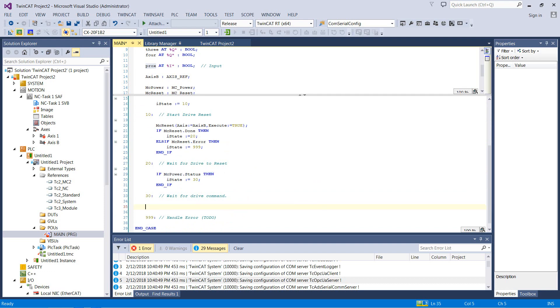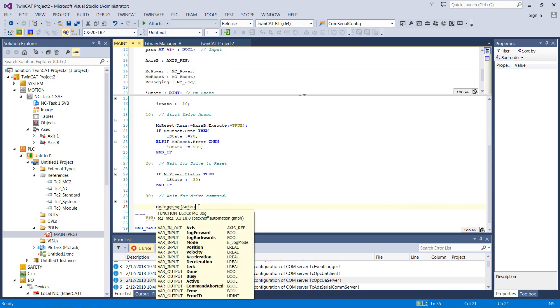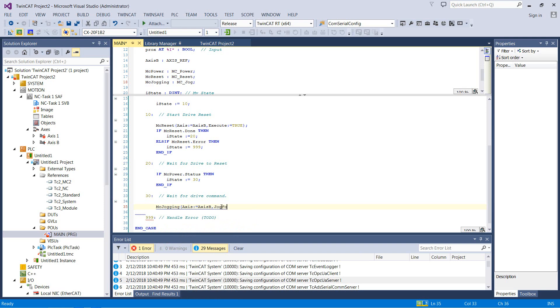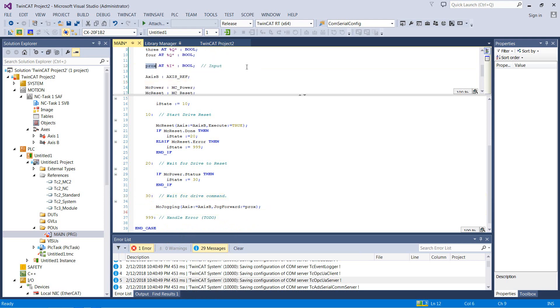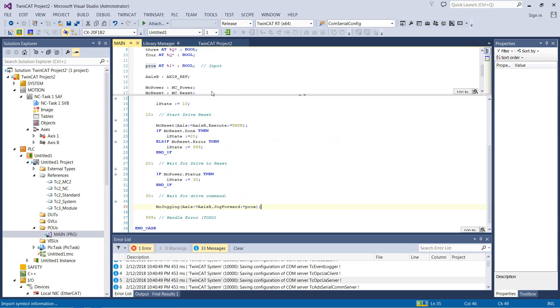Then we'll come through and reset it, and hopefully its status will come true, and we'll come to state 30 — wait for a drive command. In this case we're going to say mc jogging — I believe is what we called this — and here we need to give it the axis reference, axis B. I'm not going to get too crazy with the options because they will default to whatever NC has if you leave them blank. So I'm going to say jog forward equals prox. That jog forward is going to equal the digital input of the prox, and we're just going to jog along happily anytime that prox is set true. Let's see if that actually works — I'm going to save all, activate.